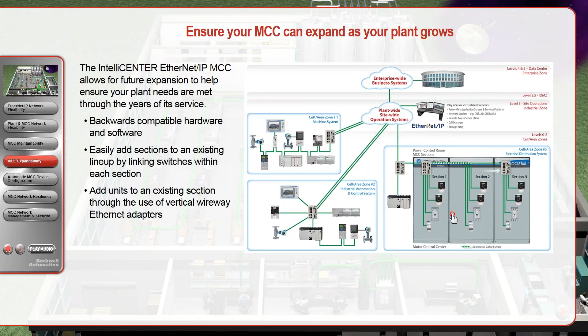Again, that expandability. When we ship our MCCs, we try to make sure you're not purchasing excess equipment you don't need. As part of our Ethernet switch optimization project in our plants, we ensure the right port count is appropriate for the number of devices connecting among sections. A switch can support up to 9 or 10 sections, and an MCC can support up to 10 switches in a single uplink, all coming together into one Stratix switch connected to your ControlLogix or CompactLogix processor.